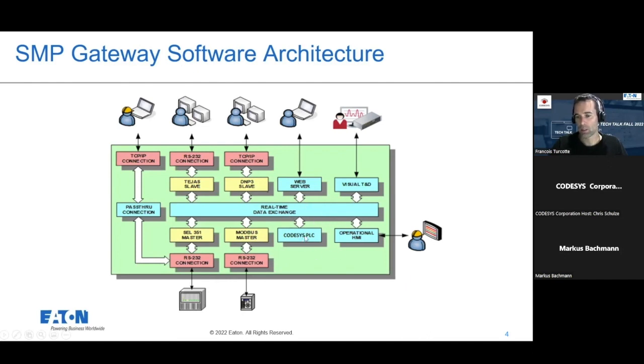You see the CODESYS PLC is right there, and it's going to interact directly with what we call the RTDX, or the real-time data exchange, to receive point information and be able to send a command to that layer. If we want to do any processing on a point received from an IED from the field, we can implement that logic in the CODESYS. Let's say I want to operate a breaker if I receive a status value from another device. So I receive an input from one device, I treat it here, and I can send a command to that other device to operate if it's needed.